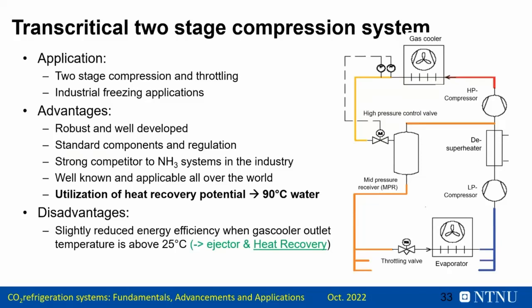And we can do a transcritical two-stage compression system also. And then this is often applied for industrial freezers, and it's very robust and developed. It's a strong competitor to ammonia systems, and it is highly recommended to utilize the heat recovery potential up here on the high pressure stage to produce, for example, 90-degree water, which is mainly also needed at these kinds of plants.